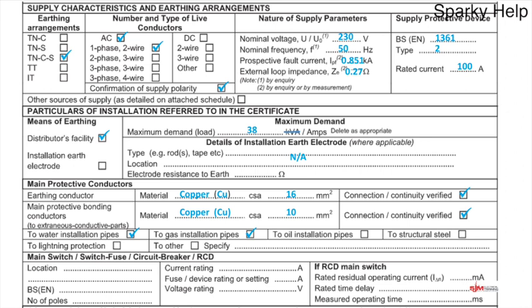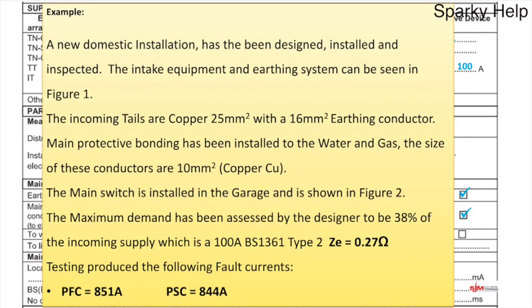Moving on down the sheet, we're getting our way through now. It says main switch, switch fuse, circuit breaker, or RCD. These are all your main disconnection points of the installation, whatever they happen to be. So the first thing to ask for is the location, so we need to go back and look to see where it is, and we can't just say in the distribution board. We actually physically want to know whereabouts it is. Is it the cupboard under the stairs? I don't know. Most convenient place if ever to put one.